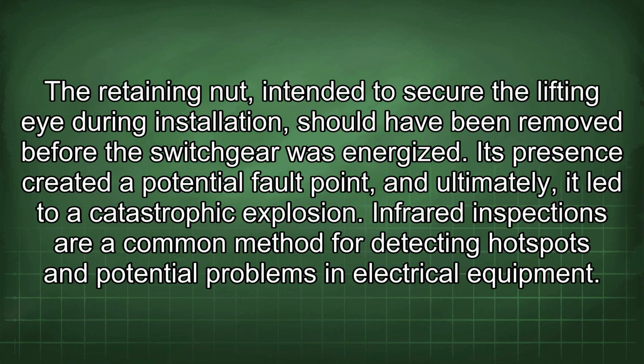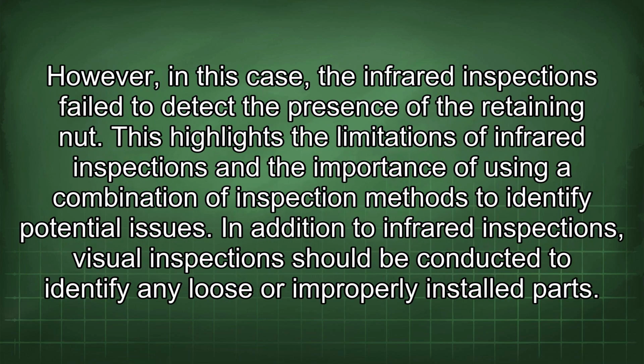The retaining nut, intended to secure the lifting eye during installation, should have been removed before the switchgear was energized. Its presence created a potential fault point, and ultimately, it led to a catastrophic explosion. Infrared inspections are a common method for detecting hotspots and potential problems in electrical equipment. However, in this case, the infrared inspections failed to detect the presence of the retaining nut.